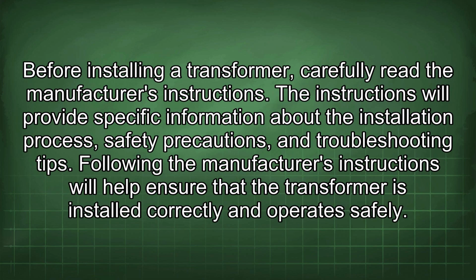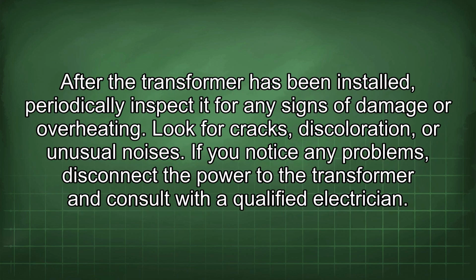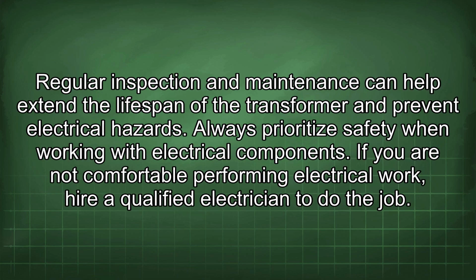Before installing a transformer, carefully read the manufacturer's instructions. The instructions will provide specific information about the installation process, safety precautions, and troubleshooting tips. Following the manufacturer's instructions will help ensure that the transformer is installed correctly and operates safely. After the transformer has been installed, periodically inspect it for any signs of damage or overheating. Look for cracks, discoloration, or unusual noises. If you notice any problems, disconnect the power to the transformer and consult with a qualified electrician. Regular inspection and maintenance can help extend the lifespan of the transformer and prevent electrical hazards.